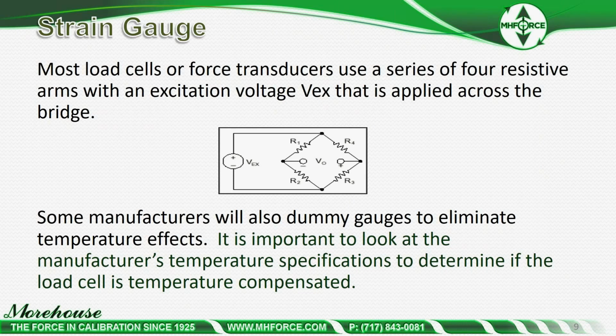But looking at that, most load cells or force transducers use a series of 4 resistive arms with an excitation voltage that is applied across the bridge. Some manufacturers will also use dummy gauges to eliminate temperature effects. It is important to look at the manufacturer's temperature specification to determine if the load cell is temperature compensated. Some will even say they are, and they're not, so it's important to test for this.